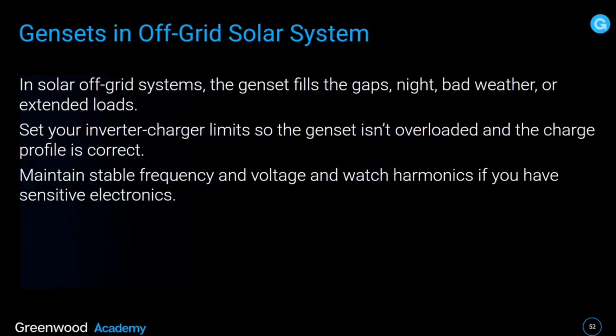In solar off-grid systems, the genset fills the gaps: night, bad weather or extended loads. Ideally, you set your inverter charger limit so the genset isn't overloaded and the charge profile is correct. Maintain stable frequency and voltage and watch harmonics if you have sensitive electronics.